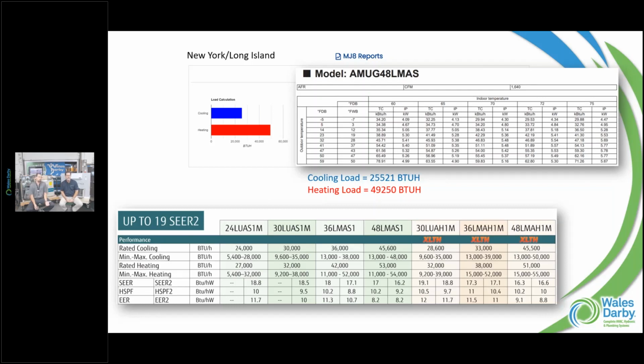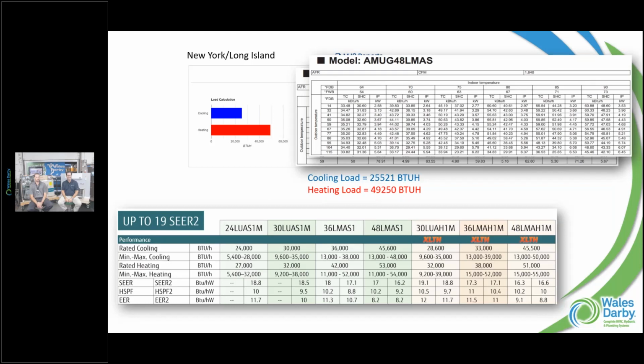We might be fine in heating, but what's going to happen if I put a 4-ton system in, this 48,000, and it covers the heating load for most winters? Now I've got a cooling load of 25,000 BTUs. So now we look at the cooling side of that chart. Same thing, just a couple more columns. In our design case we're talking an 86-degree day, with the 70-degree set point. We'll go with that.